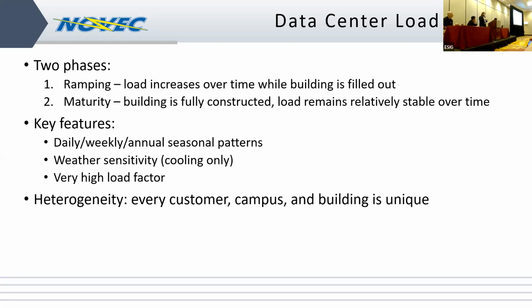Eventually it gets to a point where it's mature, all the servers that are going in there have gone in. At maturity the load is for the most part stable, but not totally flat. That's when folks say oh it's a flat load. Not quite. You do see regular seasonal fluctuation, you do see weather sensitivity, but yes, the load factor regardless of what time scale you're looking at tends to be very high.